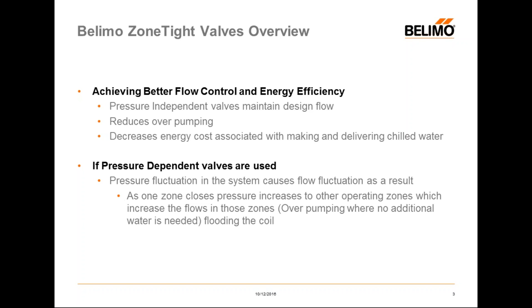As one zone closes, the pressure in that zone will increase the pressure in an operating zone, which will result in additional flows being delivered to the zone that is operating — however, it's not required. This condition is known as flooding the coil.